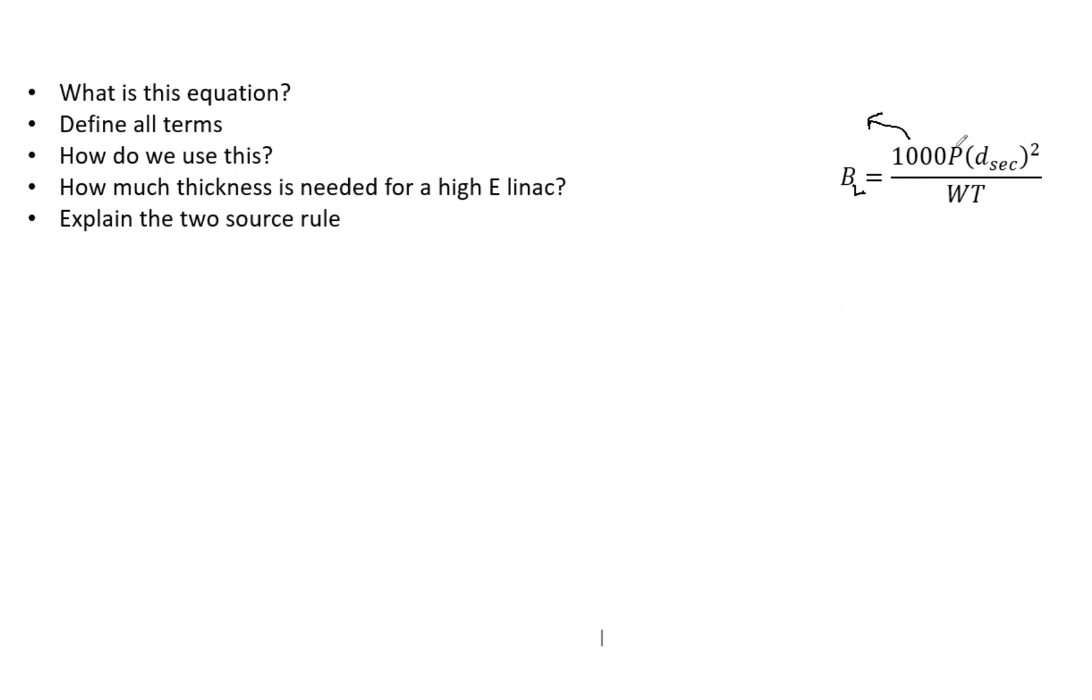Here we have our permissible dose rate, just like all of our other shielding calculations. D_sec right here is the distance from isocenter to 0.3 meters beyond the barrier. Always remember that is 0.3 meters beyond, and of course, that is squared. W we have as our workload. And T is our occupancy factor. Also note, for head leakage, we do not have a use factor because the head leakage is coming from essentially almost isotropic. So you do not have a use factor in this equation.